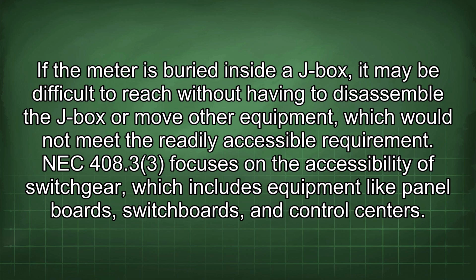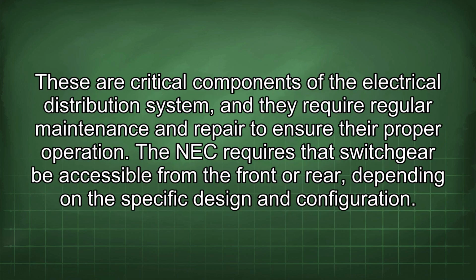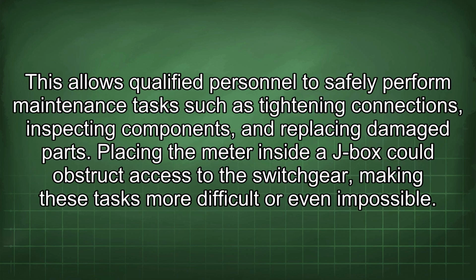NEC 408.33 focuses on the accessibility of switchgear, which includes equipment like panel boards, switchboards, and control centers. These are critical components of the electrical distribution system, and they require regular maintenance and repair to ensure their proper operation. The NEC requires that switchgear be accessible from the front or rear, depending on the specific design and configuration. This allows qualified personnel to safely perform maintenance tasks such as tightening connections, inspecting components, and replacing damaged parts. Placing the meter inside a J-box could obstruct access to the switchgear, making these tasks more difficult or even impossible.